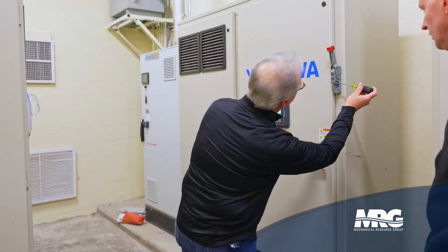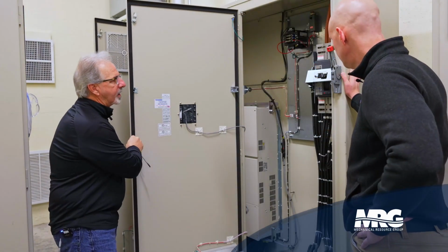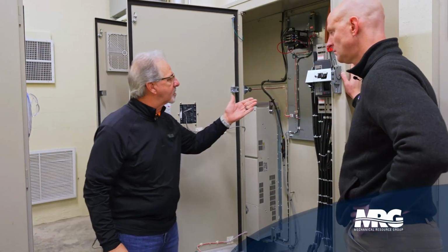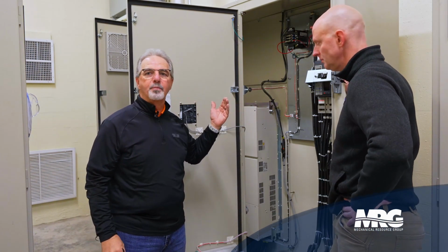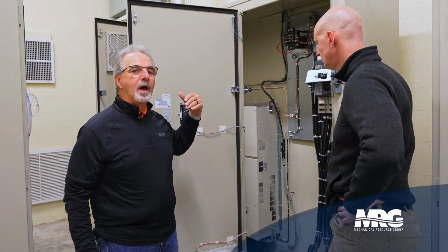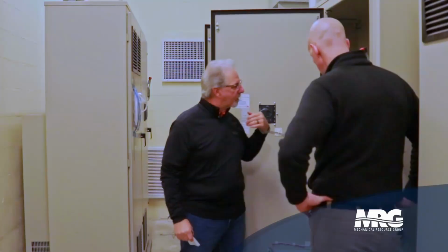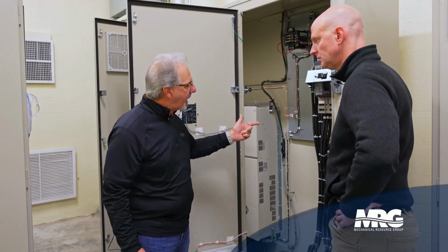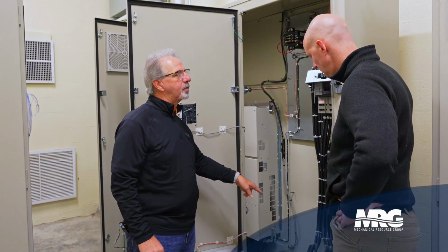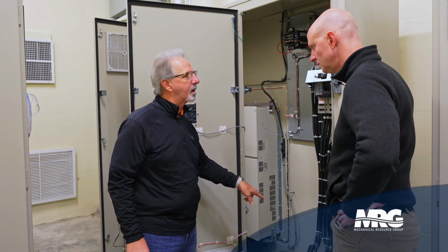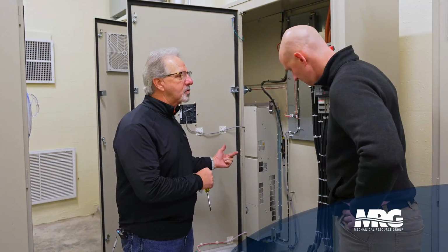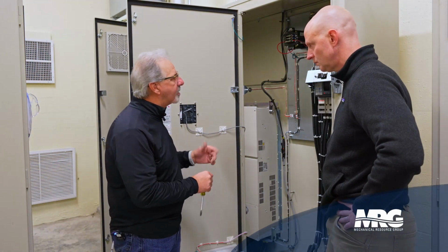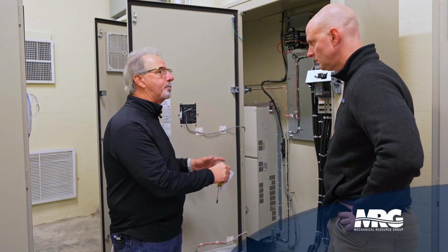Yeah. But I want to go ahead and take some time and open up the door. And here on the front end, John, we see that we have the main service disconnect. Now this is a 1,000 amp breaker. And then what we do is we come out of the 1,000 amp breaker and we go to 1,400 amp fuses to protect the front end of the drive. Now, if you'll notice, as we come out of this disconnect, we come down and we hit the 3% line reactor I was talking about. When we move over to the other side, I'll show you the drive, but this right here gives you a good idea of our input power scheme.